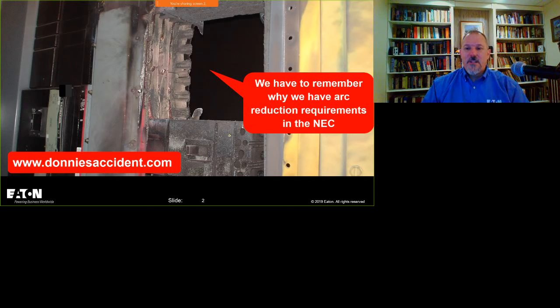Yeah, very stiff electrical system. Yes, Tim, 83 MVA. On secondary networks, go ahead, Tim. Yeah, Tom, that's very stiff at 480 volt. That's why we have 65 kA bus bracing and 65 kA rated devices, because most utility systems are going to be less than 65 kA. And what you're looking at is probably a supply transformer, 2500 kVA. Now, on an industrial system or a spot network where you parallel transformers and you get 3000 kVA at 480 volt or 5000 kVA at 480 volt, you can see some of those 100 kA short circuit currents. But rarely on a utility system will you see one exceeding 65 kA unless it's like a metropolitan area or a spot network.